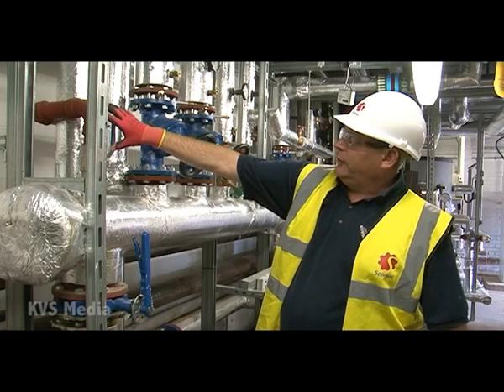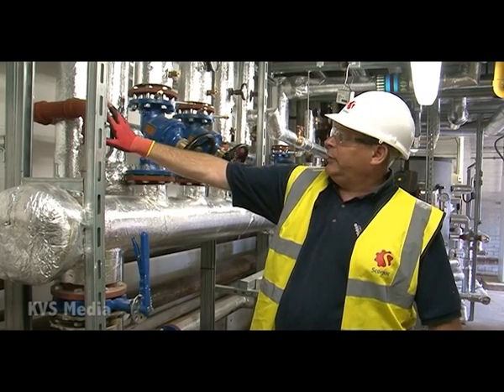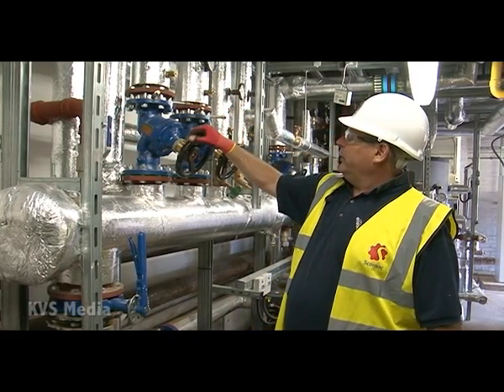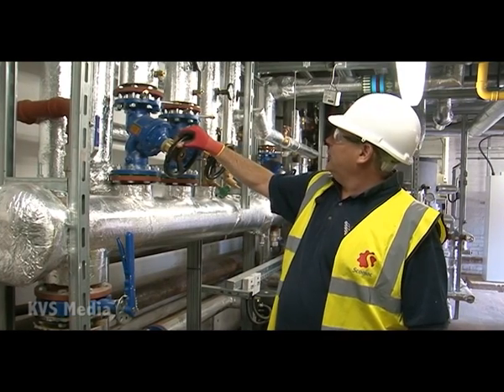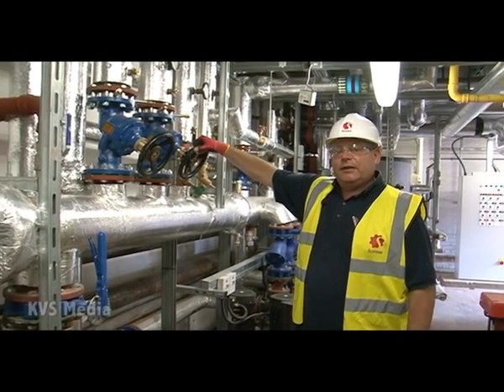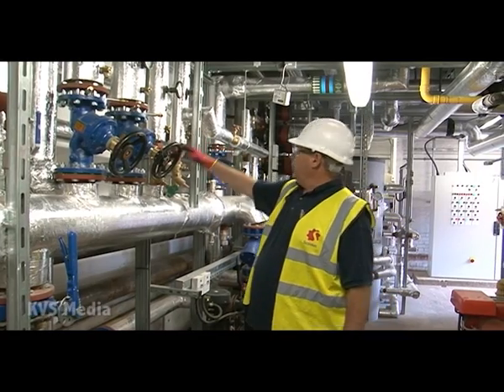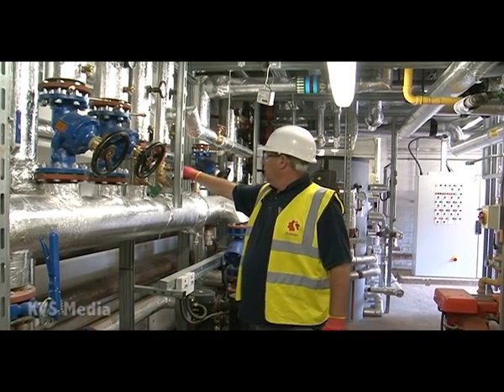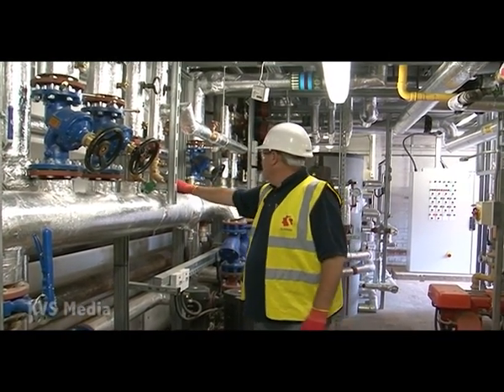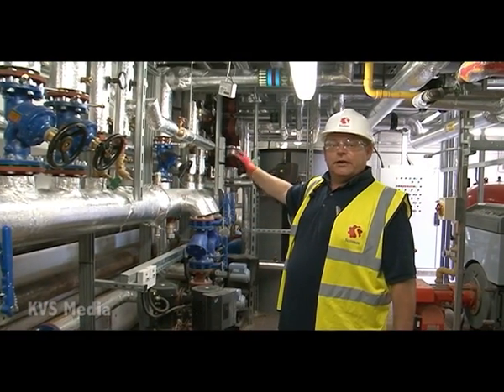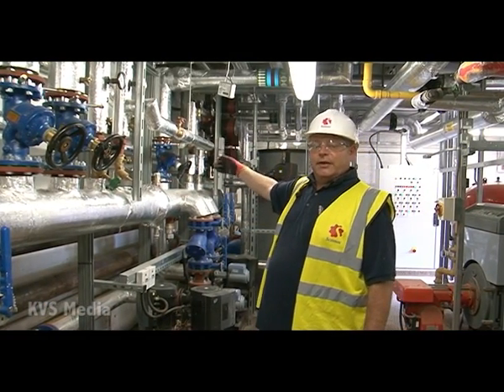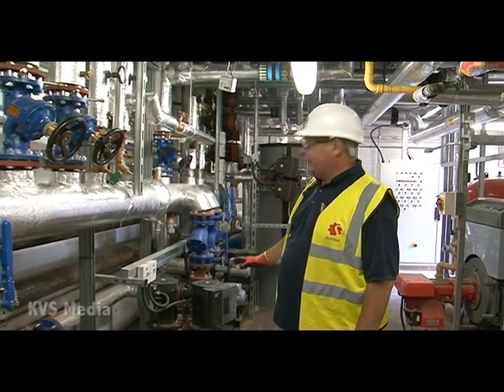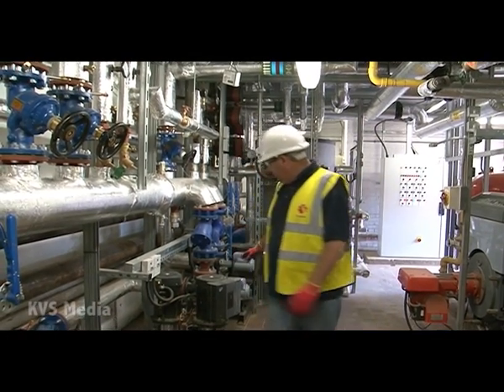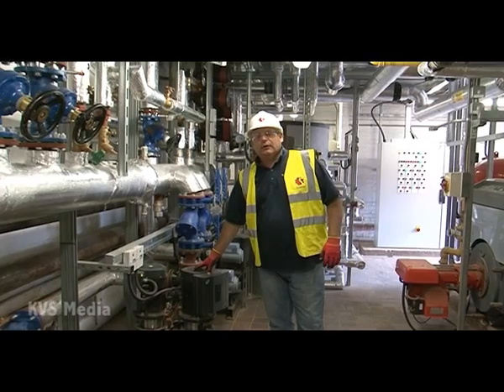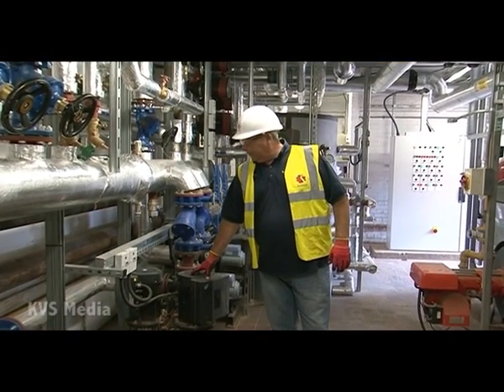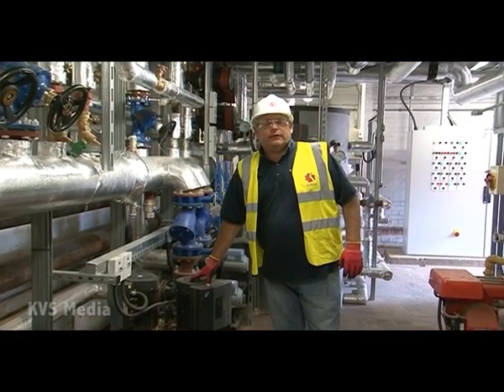These are all numbered and labelled on the charts. The second one is the kitchen return. The next one along is block D return. And then we go to block A return and block B return. It's the same principle on the flow. It goes kitchen, block A, block B, block D. Pumps that we've installed: these are the main pumps which feed the new block D and also the underfloor heating systems in the hub.